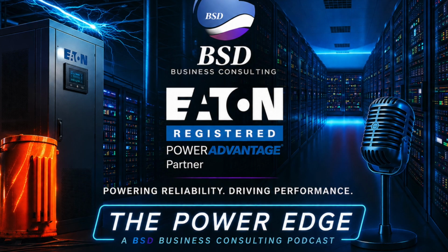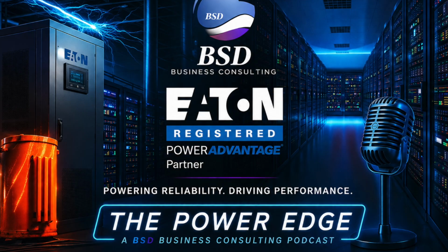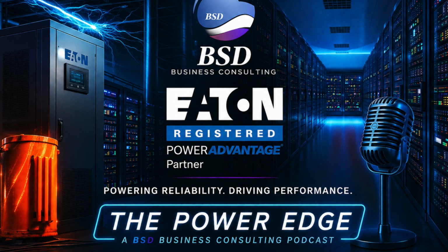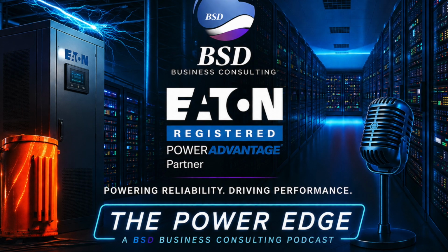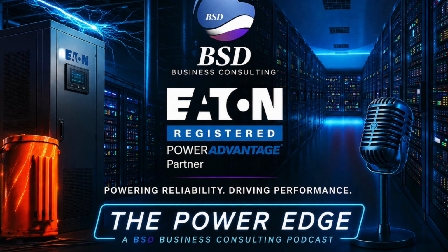So by switching to an 800-volt HVDC system, Eaton and NVIDIA are eliminating those inefficient conversion steps. Precisely. By distributing high-voltage direct current directly to the racks, they streamline the power path. It reduces energy waste, lowers the heat generated by the power distribution equipment itself, and allows the facility to pack more computing power into a smaller physical footprint. Eaton is integrating their intelligent power distribution, backup solutions, and digital management software directly with NVIDIA's reference designs.